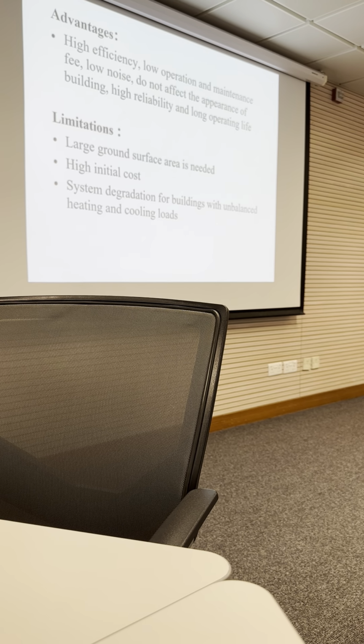Even in Hong Kong, ideally, the ground temperature is 22 degrees Celsius, but the outside air is 35 degrees Celsius in summer, in July and August. Of course, the heat pump system efficiency, or we call it COP, is higher. That's the main reason. High efficiency. Why do we call it low operation and maintenance fee? Because we don't use chilled water for cooling. We don't use air-cooled equipment, heat exchangers, and so on. Very reliable, I must say. We just need a pump. And the underground pipeline is also cheap. No noise, of course. Do not affect the appearance of buildings.